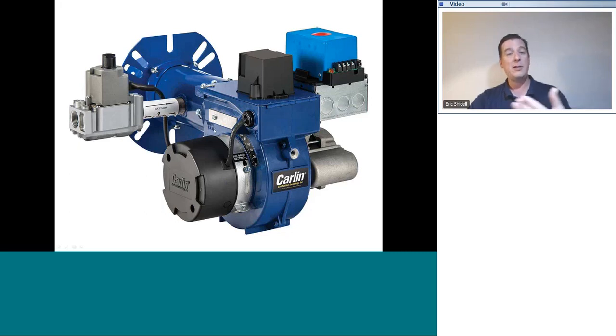Some burners have independent adjustments for primary air and for secondary air. And that's what I was talking about earlier. When tuning a burner like this, you need to have the correct ratio of primary air to secondary air. And to do that, you need a draft gauge to measure that draft and a combustion analyzer to get the right ratio of fuel to air mixture. That's why we talked about products of combustion originally. That's why we're concerned with the products of combustion. When we take a look at chemically and analyze the products of combustion, we can gauge whether or not the mixture of fuel and air was appropriate.